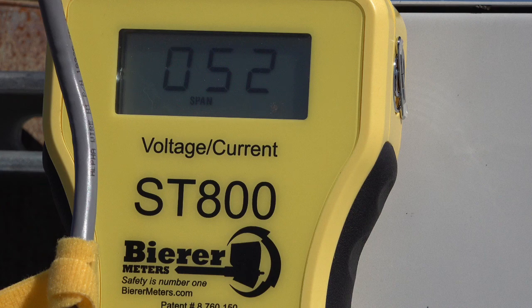Or it could be a combination of both small cable and a long service distance. Whichever the case may be, you're looking for consistency between all three connections. As an example, if our first test between the neutral conductor and one of the hot conductors was only able to achieve 600 amps, then we would expect to see 600 amps between the same neutral connection and the other hot conductor as well. If the neutral is the same size conductor as both hot conductors, the connections between both hots would also expect to see 600 amps.